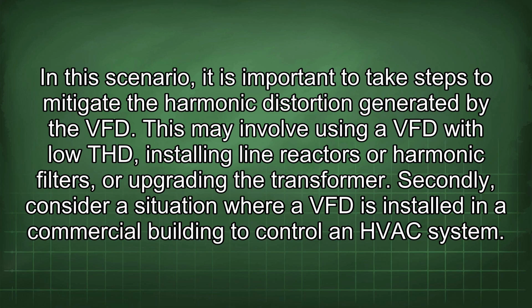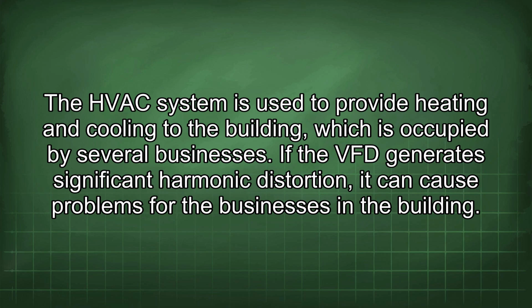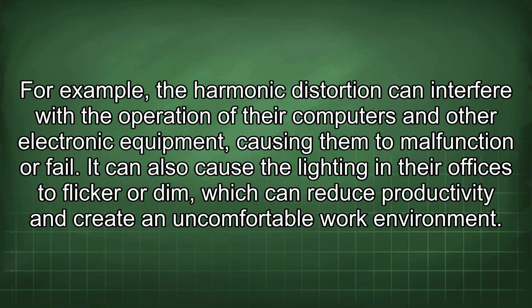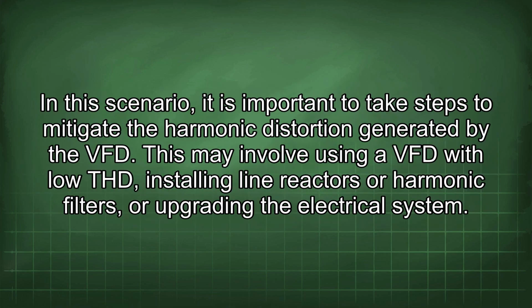Secondly, consider a situation where a VFD is installed in a commercial building to control an HVAC system. The HVAC system is used to provide heating and cooling to the building, which is occupied by several businesses. If the VFD generates significant harmonic distortion, it can cause problems for the businesses in the building. For example, the harmonic distortion can interfere with the operation of their computers and other electronic equipment, causing them to malfunction or fail. It can also cause the lighting in their offices to flicker or dim, which can reduce productivity and create an uncomfortable work environment. In this scenario, it is important to take steps to mitigate the harmonic distortion generated by the VFD. This may involve using a VFD with low THD, installing line reactors or harmonic filters, or upgrading the electrical system.